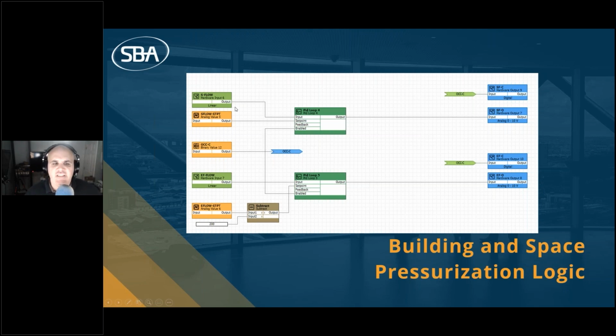All right, so this is a basic volumetric offset program. You've got supply flow and supply flow set point going into a PID loop. You've got occupancy driving the supply fan and exhaust fan commands. You've got the 0 to 10 volt signal to the VFD driving the supply fan and the exhaust fan. And you've got this exhaust flow over here, and you've got a set point going into a subtraction block, and you've got that subtraction block providing a volumetric offset. So this would create a positively pressured environment because you're going to be supplying more air than you're exhausting. If you wanted to create a negatively pressured environment, then you would simply exhaust more air than you're supplying. That's the basics of building and ultimately space pressurization.